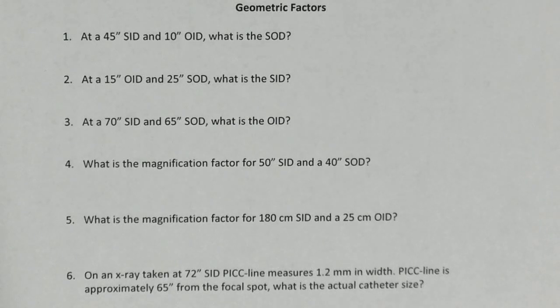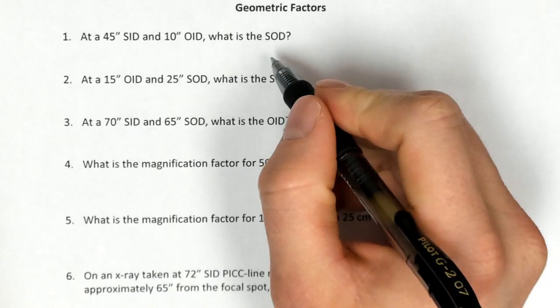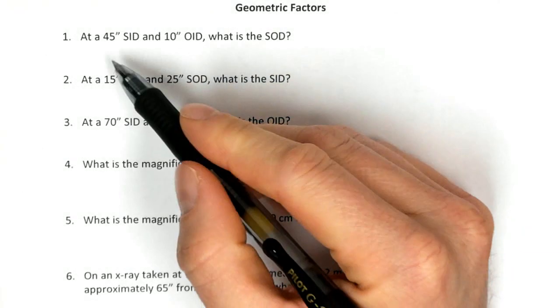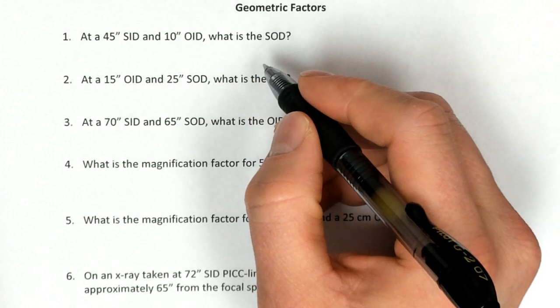Let's spend a little bit of time talking about geometric factors and the way to calculate some of these different technical considerations for our images. So this first problem is asking us, at a 45-inch SID and a 10-inch OID, what is the SOD?